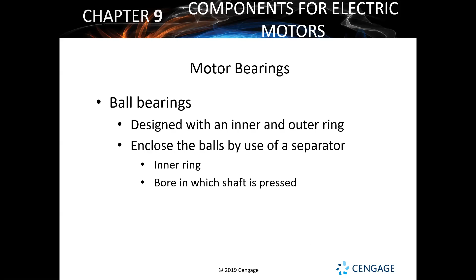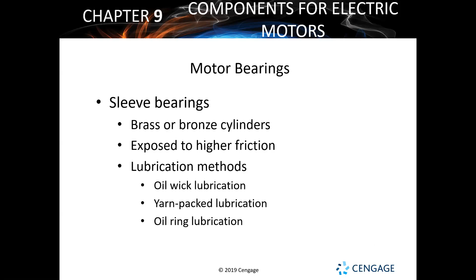So sleeve bearings, this is what we're going to see more often. That small ring that I was showing 2 slides ago, that is used in residential systems, that is your sleeve bearing. It's usually going to be lubricated from the factory. It's just going to be smooth metal that allows for good, quick rotation constantly throughout the system. So they're really versatile. They work really well. And the nice thing about a sleeve bearing is it's very quiet. So especially for blower motors and for motors for moving air inside of a building, a sleeve bearing moves the air more quietly than it would with a ball bearing motor.